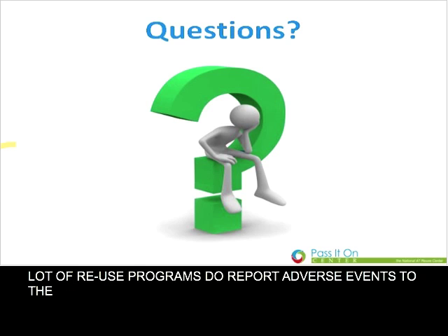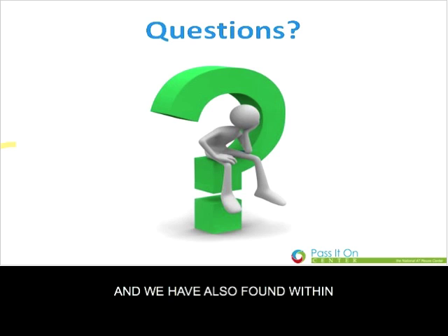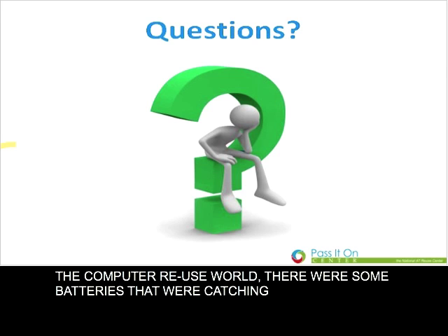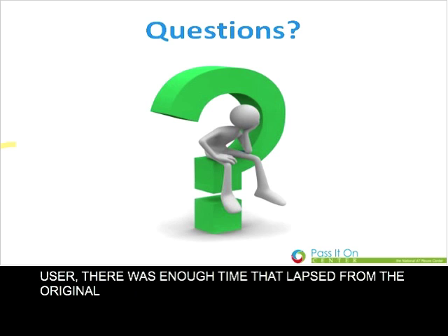Okay. So Owen, it looks like you're asking me, did I say that reuse programs do not have to report adverse events to the FDA? I did not say that. What I said is that a lot of reuse programs do report adverse events to the FDA. It's not a requirement, but it's a sign of a good program to do that.